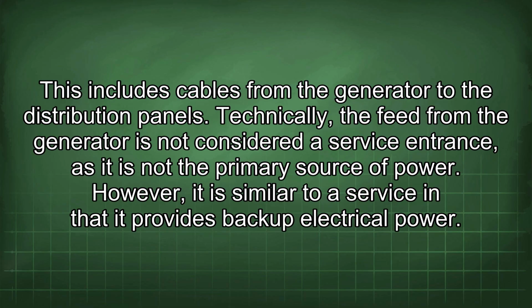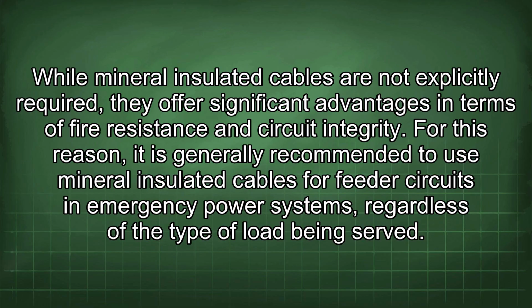Technically, the feed from the generator is not considered a service entrance, as it is not the primary source of power. However, it is similar to a service in that it provides backup electrical power. While mineral-insulated cables are not explicitly required, they offer significant advantages in terms of fire resistance and circuit integrity. For this reason, it is generally recommended to use mineral-insulated cables for feeder circuits in emergency power systems, regardless of the type of load being served.